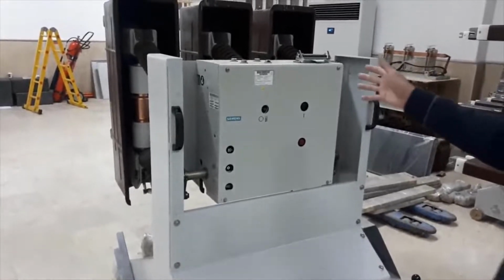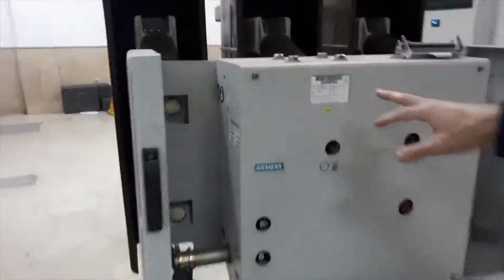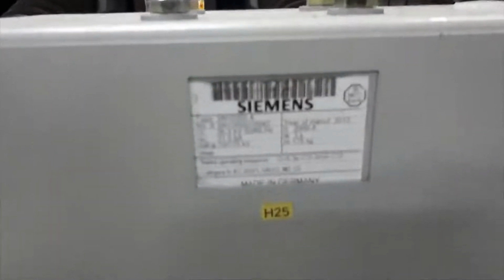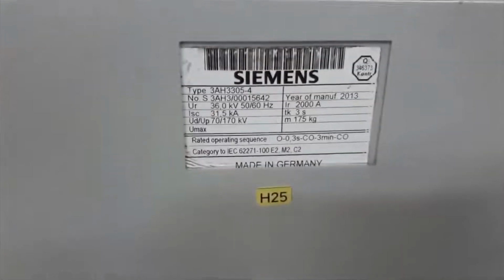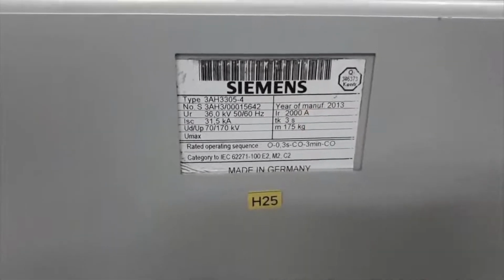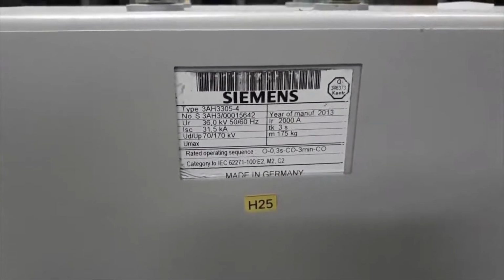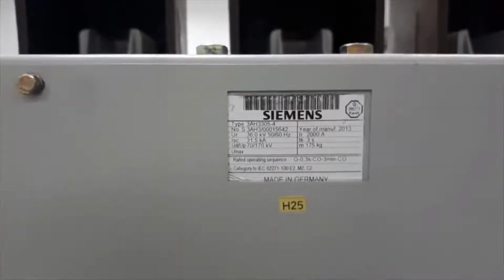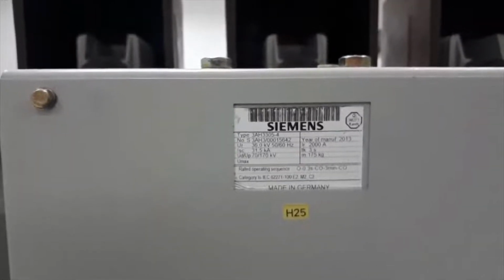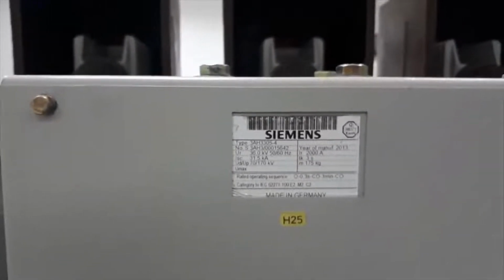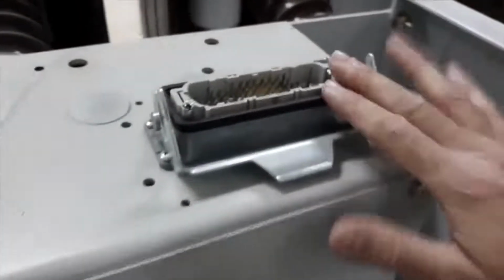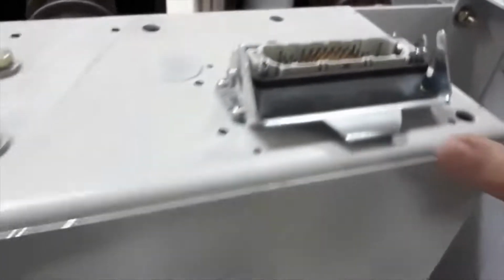And this is the 33 kilovolt breaker that you can see here. Its nominal voltage is 36 kilovolts and its nominal current is 2 kiloamperes. It is manufactured by Siemens and is mounted on a trolley, and we can rack in and rack out the breaker to be mounted inside the switchgear. Here is the breaker control socket. From here, the internal control circuitry of the breaker is connected to the switchgear.